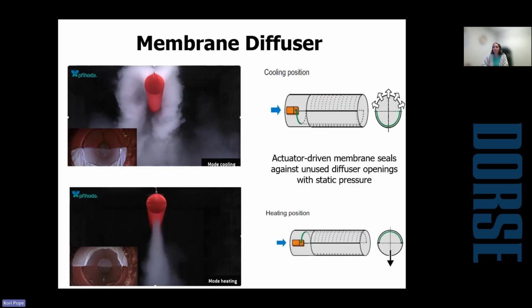So up next, we have our membrane diffuser for air distribution. The membrane diffuser is an unusual product, but it is a great solution for doing heating and cooling out of the same duct. So the way that this works is it is a permeable duct that has a non-permeable sleeve on the inside. And that non-permeable sleeve rides on a two-position actuator. So when that sleeve is on the bottom of the duct, it allows cooling out of the top, and vice versa. When that sleeve is on the top of the duct, it allows heating out of the bottom of the duct.